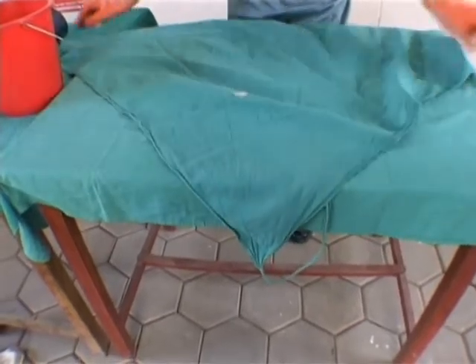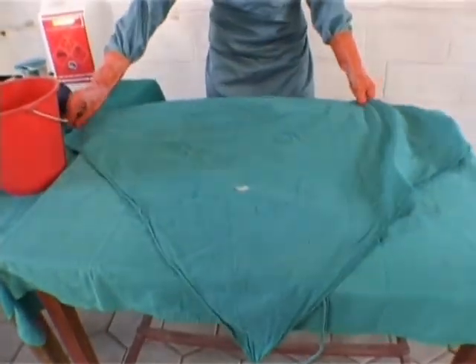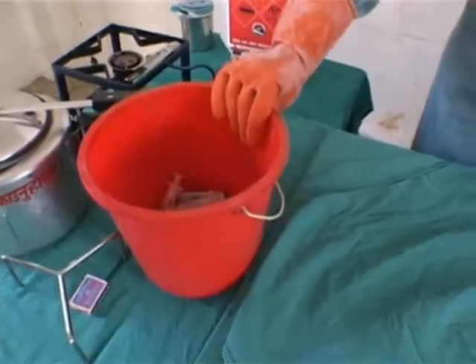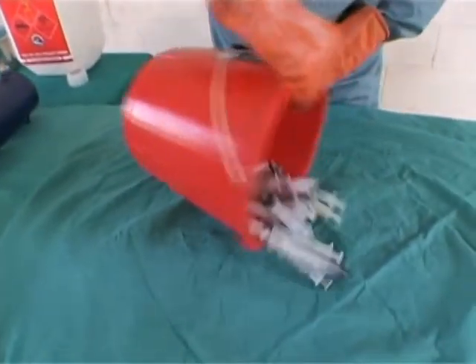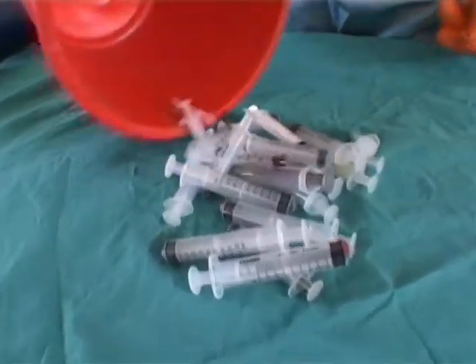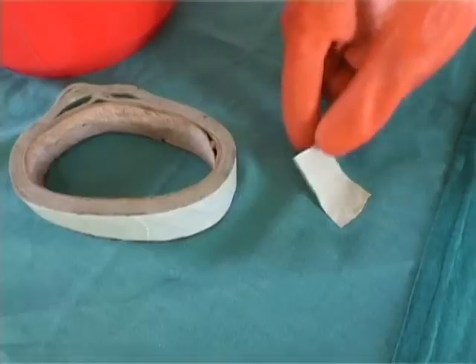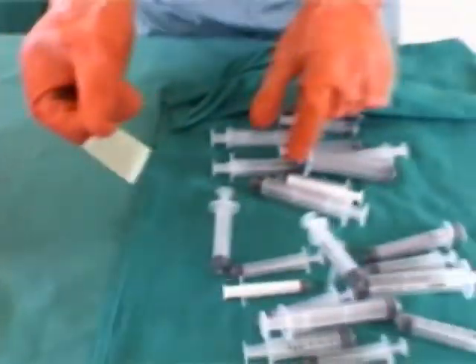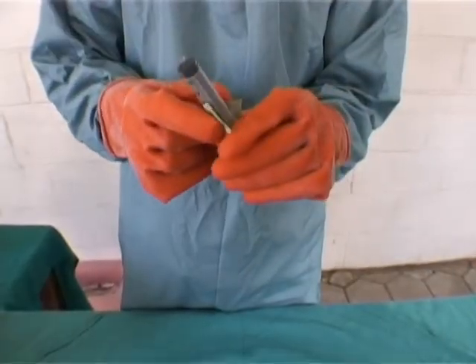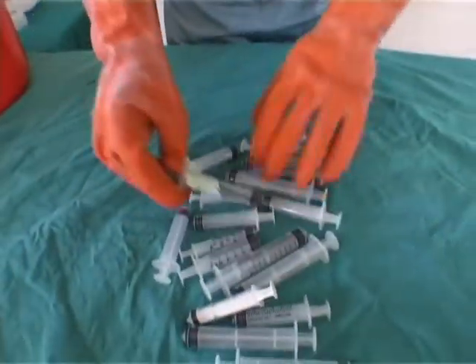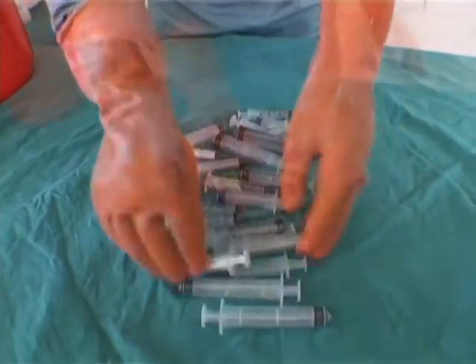Step 3 is to wrap the destroyed syringes in an appropriate cloth. In order to prepare the destroyed syringes for autoclaving, first wrap them in a thick cotton cloth dedicated exclusively for the purpose of autoclaving. It is important to place a small piece of sterilization indicator tape around at least one syringe. This tape will be used to verify the successful sterilization.